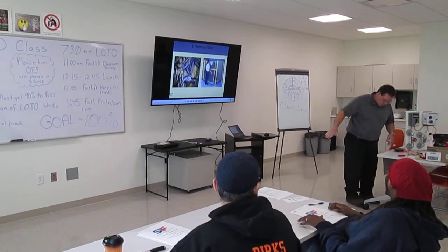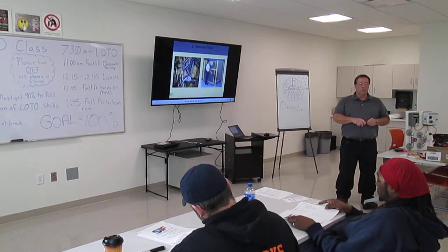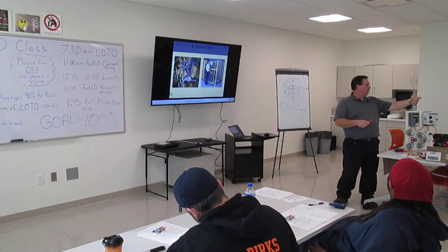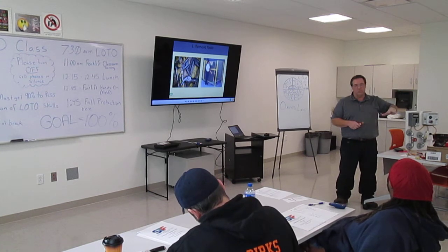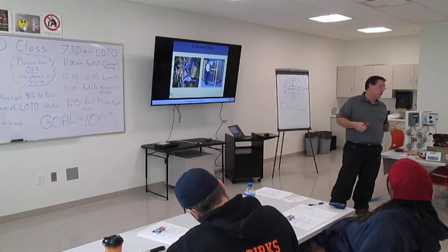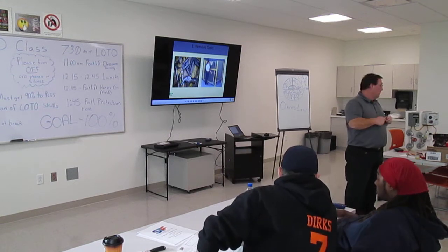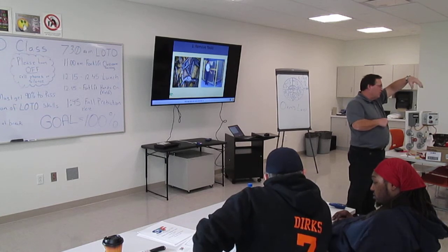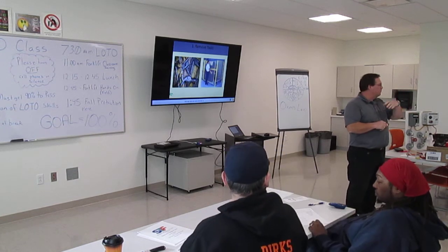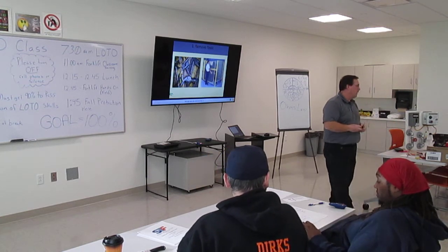When I was working on the slope, I was an electrical field engineer up there, and we had the construction crew, we had quality control, and we had quality assurance. So three different groups had to look at every piece of equipment before you could energize it, or turn it on, or do anything to it. We put in a 75 kVA transformer. The electrician left his crescent wrench phase to phase on top, inside. We buttoned it all up. Those three groups looked at it, we powered it up, and boom, all the magic smoke came out.